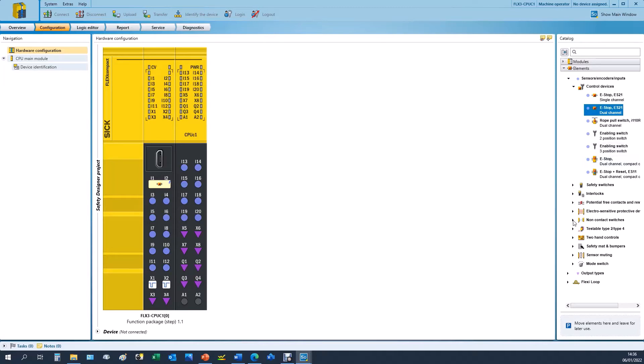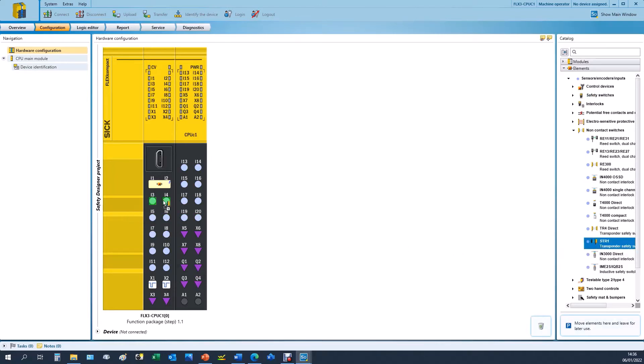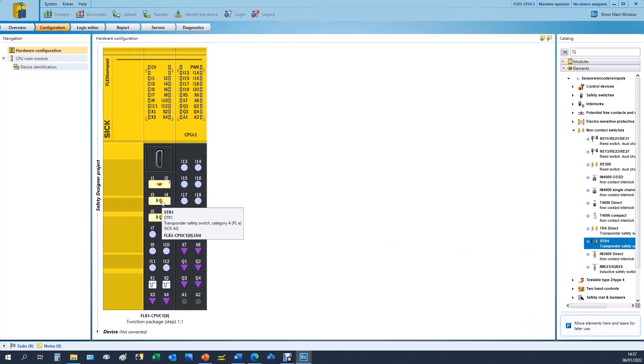Now we want to add two non-contact RFID switches which SICK provide in the STR1 series. So these are transponder safety switches which will have OSSDs, which means that they don't require test pulses and you can achieve Category 4 PLe with these individual devices.